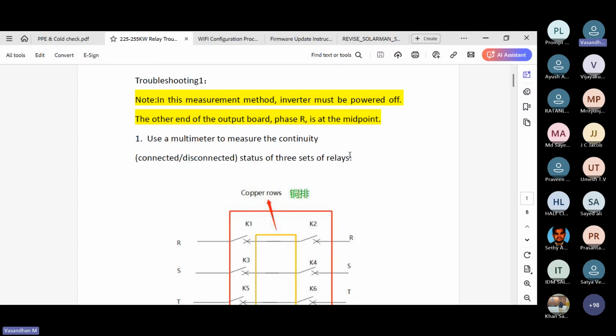So now I will continue with the relay fail. How to check the relay board? Whenever you open the inverter, first switch off both AC and DC, then open the lid cover. Then you can remove the display board cable. After that, keep the inverter lid to one side. Then you have to check whether there are any burns, any smell, or any burnt particles. Something you have to check.